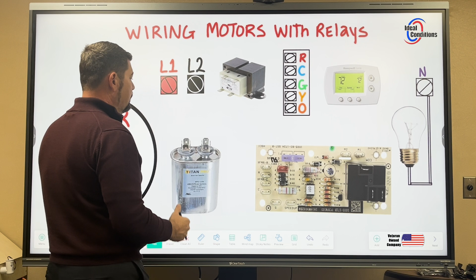And I like to wire my transformer first just because that's what I've been doing on these smart boards lately. Not maybe how I would do it in the field, but for this purpose, I'm going to wire my transformer because it's like 2 inches away from L2. I'm going to come down. I'm going to land one leg of power. I'm not going to jump over here to L1, because I want to finish L2.